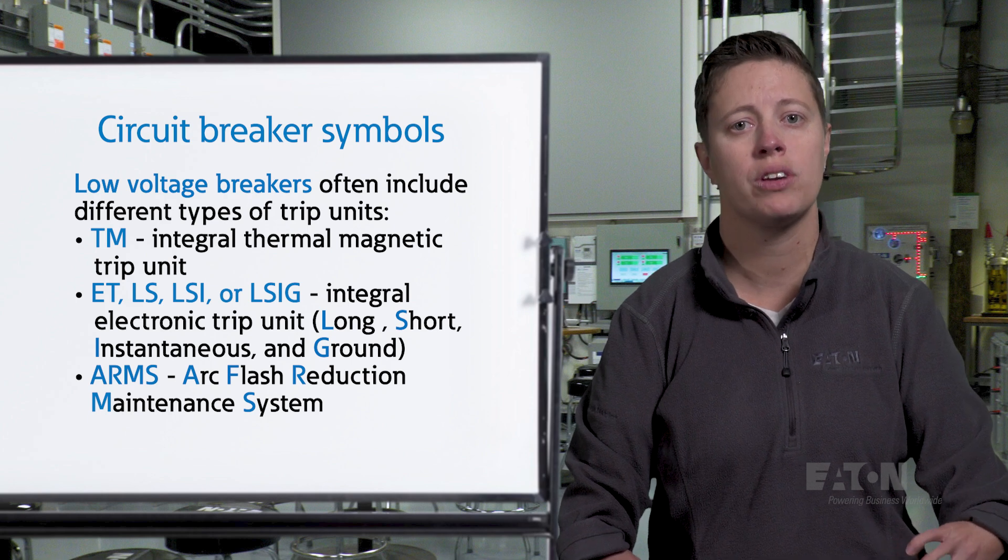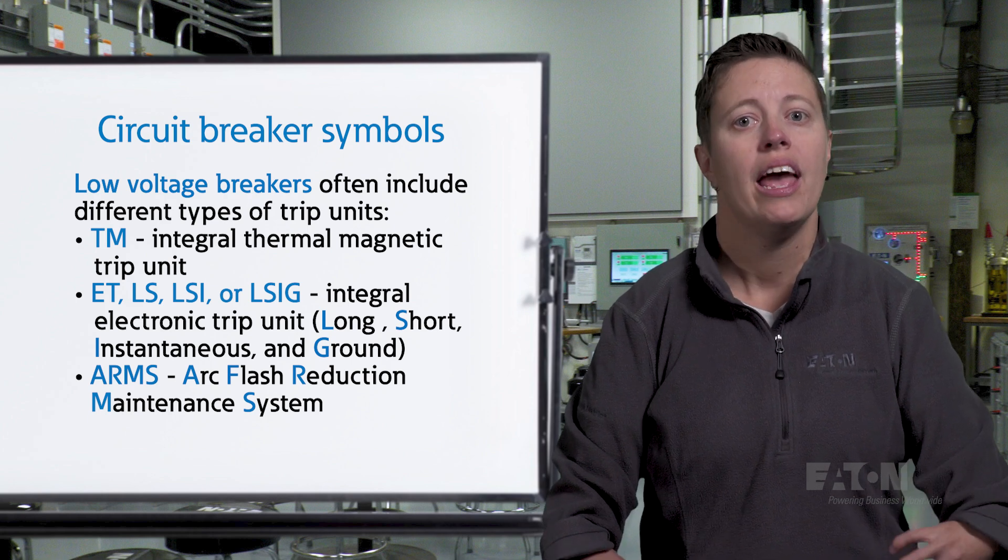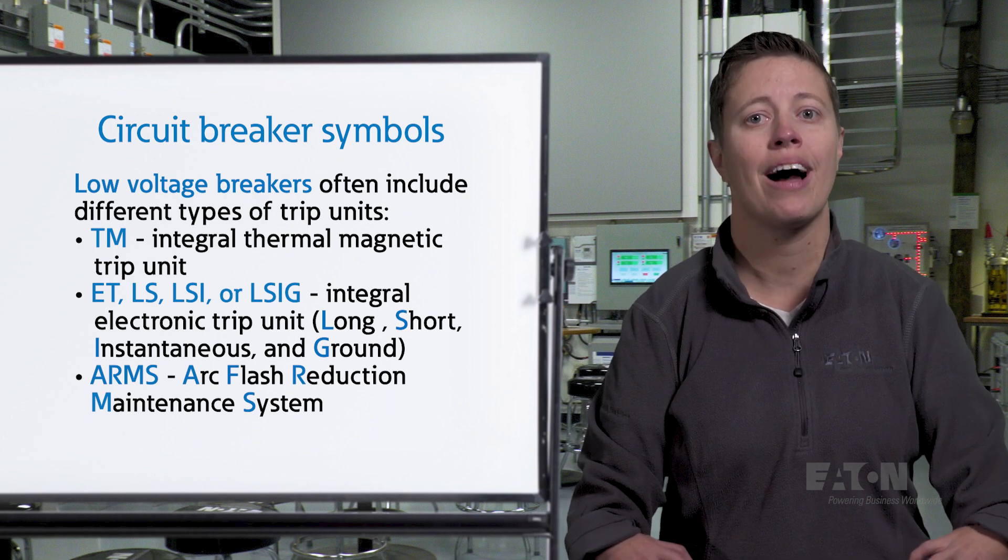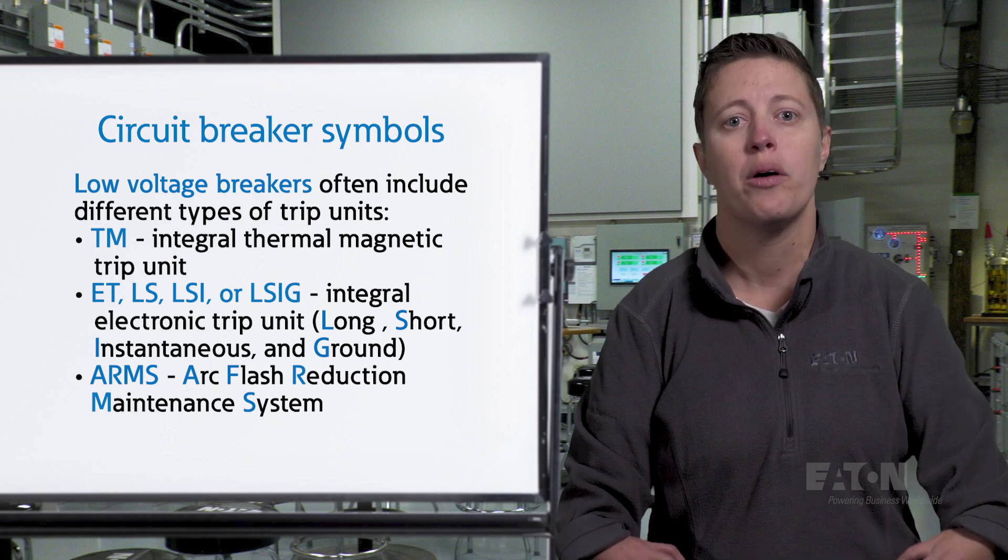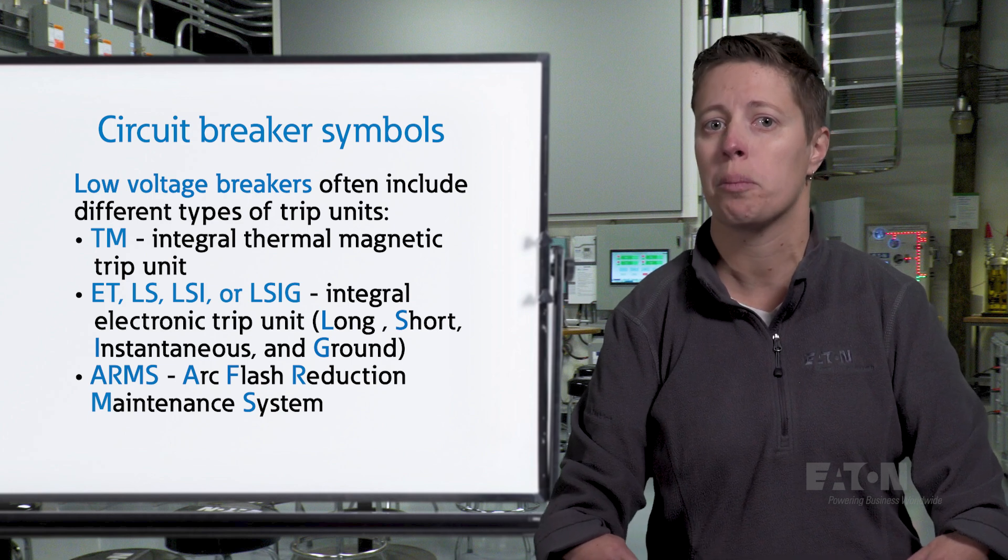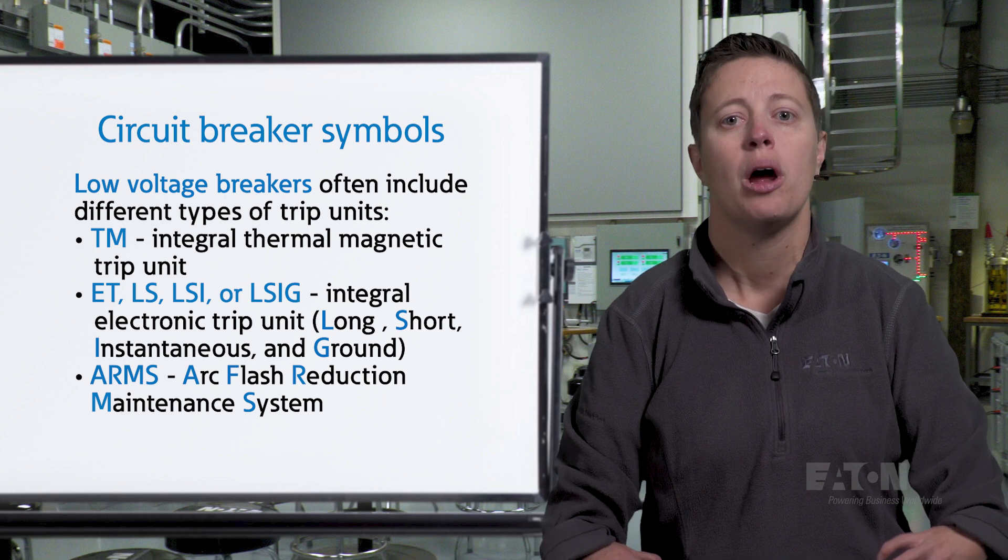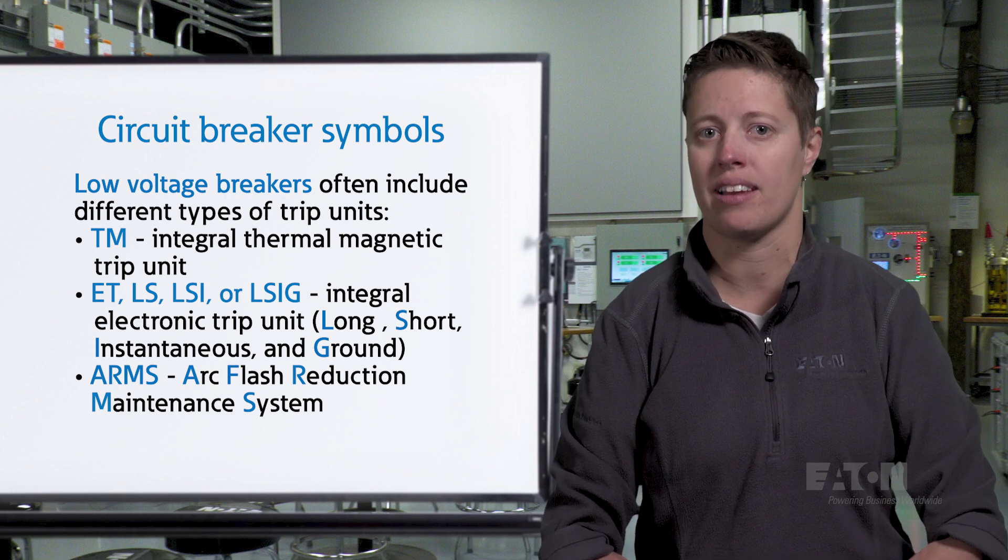ARMS stands for Arc Flash Reduction Maintenance System. Including ARMS as an option with an electronic trip unit provides a maintenance mode switch that, when activated, will trip the breaker faster than the programmable instantaneous setting at the first sign of a fault, protecting workers that may be working downstream.